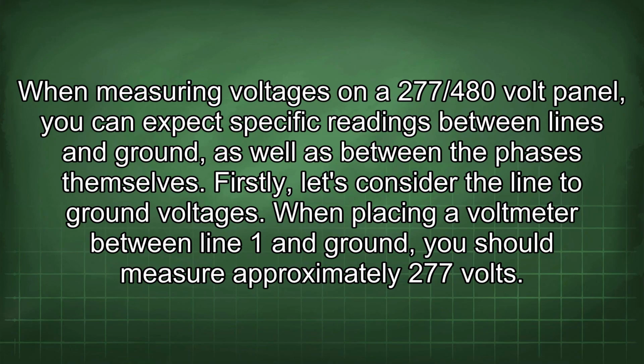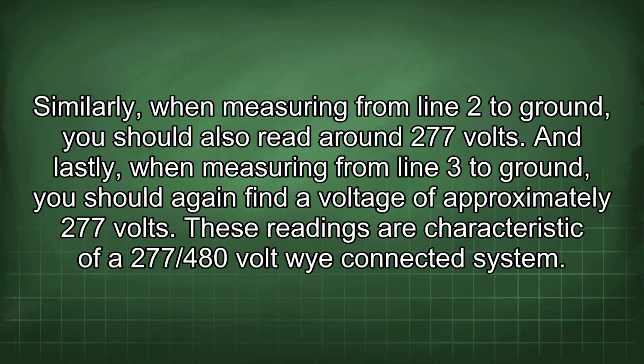When measuring voltages on a 277/480 volt panel, you can expect specific readings between lines and ground, as well as between the phases themselves. Firstly, let's consider the line to ground voltages. When placing a voltmeter between line 1 and ground, you should measure approximately 277 volts. Similarly, when measuring from line 2 to ground, you should also read around 277 volts. And lastly, when measuring from line 3 to ground, you should again find a voltage of approximately 277 volts.